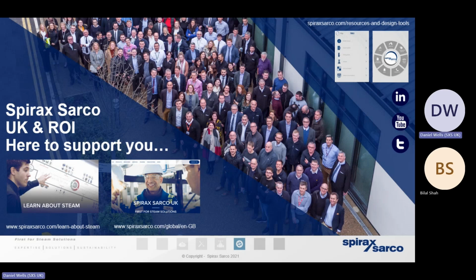When we're generally talking to a steam user, a hospital, an oil and gas plant, whatever it may be, I would anticipate around 50% of our clients have got a really good understanding of what their cost of steam is. 25%, they probably hold their hand up and they say, we've got no idea what our cost of steam is. Can you help us with that? What's most worrying is that the remaining 25% of those clients, they will tell us they know what their cost of steam is, but they will be way off the mark because they're probably basing that information on the cost of gas from 5 years ago. And as we know, since the war in Ukraine, the cost of gas is somewhere between 3 and 3.5 times what it was. So if our client is basing their cost of steam on the cost of gas from 5 years ago, they're way off the mark. So that really is one of the first questions we want to understand, the cost of steam.